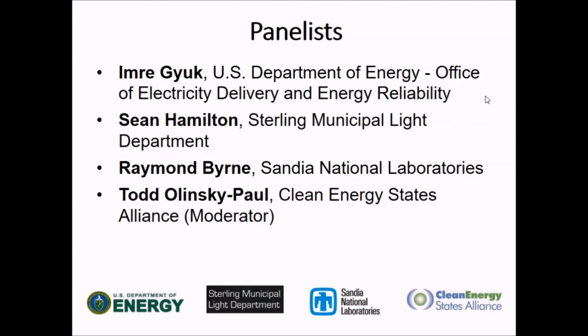Todd, I can add to that. There's a 21 peak demand load down at the building. We assumed that during a severe storm or something of that magnitude, we could reduce load - shutting down copiers, the air conditioner, or other units - to extend the life of the batteries. We assumed we could cut the load in half. Averages run around 14 to 16, and we felt comfortable we could shed 4 to 6 kW if needed in an emergency.